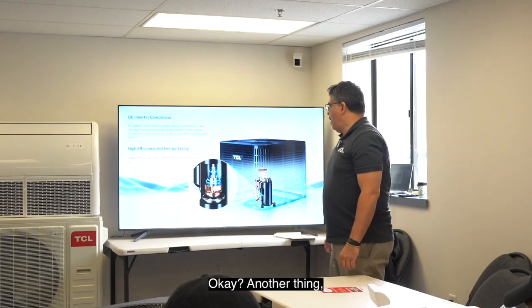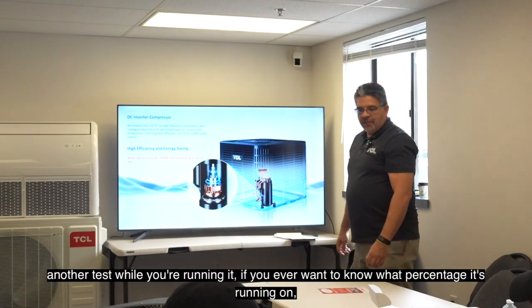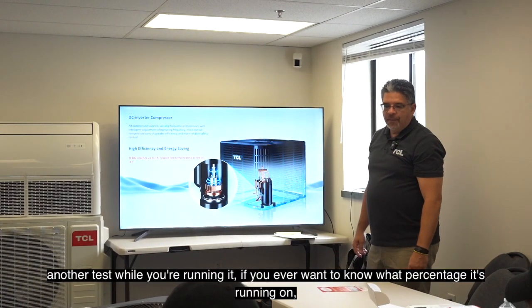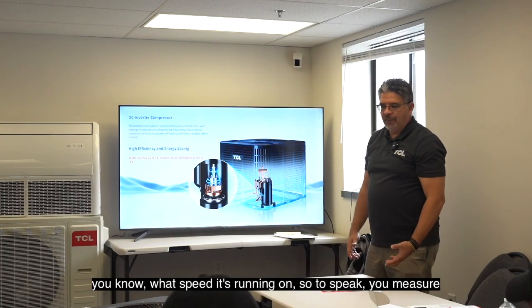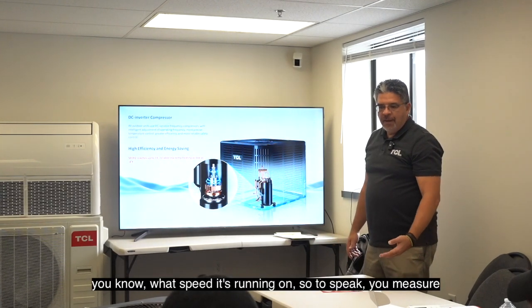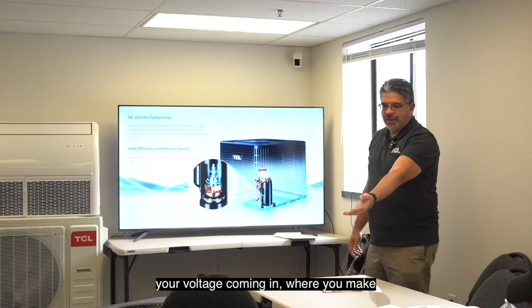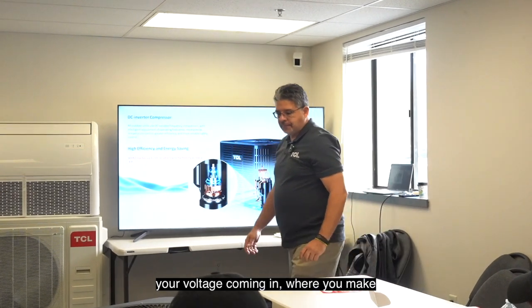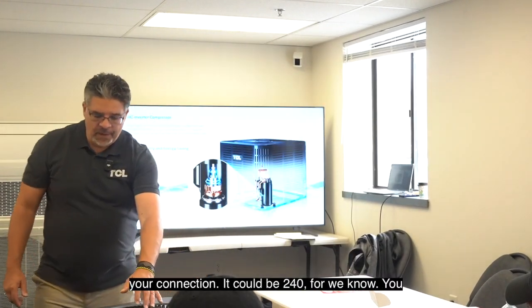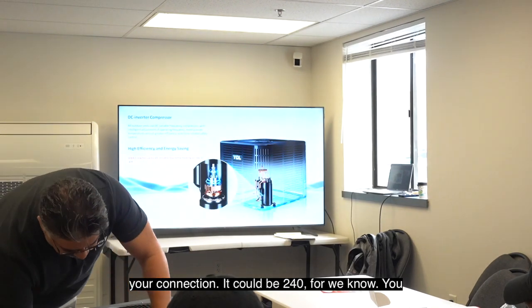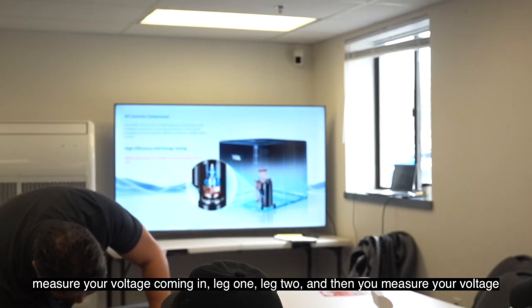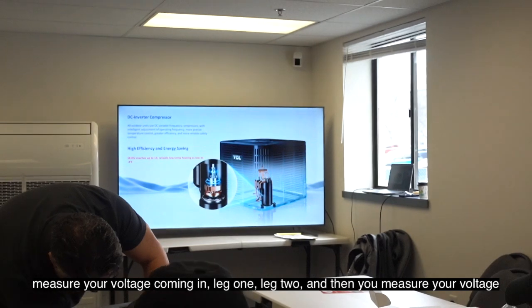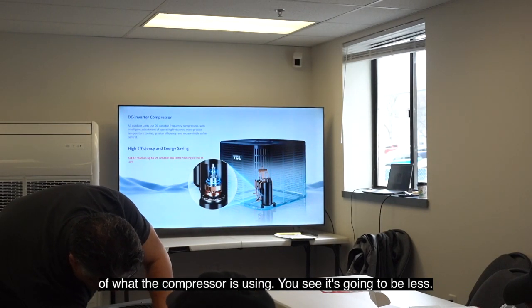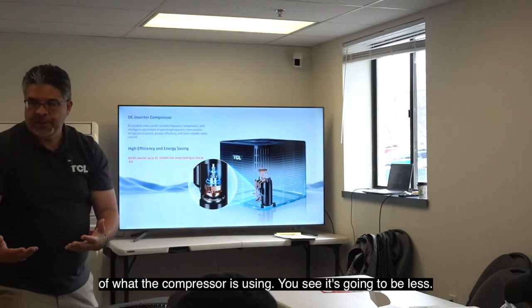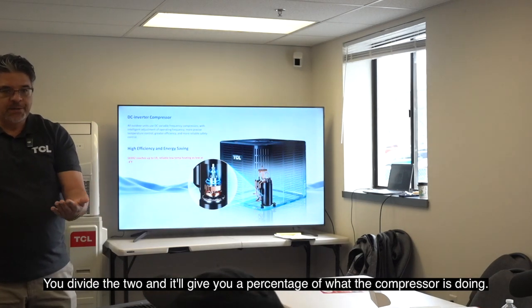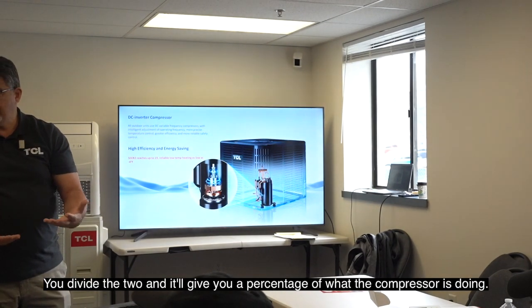Okay? Another test while you're running it, if you ever want to know what percentage it's running on, what speed it's running on, so to speak, you measure your voltage coming in, where you make your connection. It could be 240, for all we know. You measure your voltage coming in, leg 1, leg 2, and then you measure your voltage of what the compressor is using. You see it's going to be less. You divide the 2, and it'll give you a percentage of what the compressor is doing.